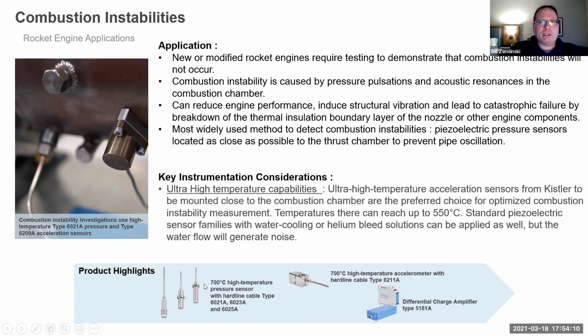Another application is combustion instabilities, where you're monitoring the pressure inside the combustion chamber, maybe even with a high temperature accelerometer. You can imagine 700 degrees C would be the requirement needed in a sensor to accomplish this, and piezoelectric technology certainly satisfies 700 C continuously, with very high performance capabilities to measure pressure and vibration at these temperatures.